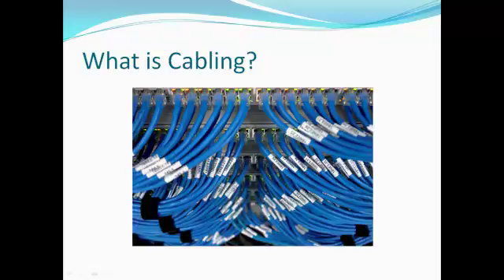Here's another great example — if you look at the actual cables themselves, the cables have been labeled for where they're going. That's going to be another big aspect of cabling. It's not just the physical bundling of all of our cables and putting the physical cable in the correct tray, but also doing labeling of the cable and labeling of the interface. So that when we go to reference our documentation, we don't actually have to go to the wire or go to the device. Our documentation should be so thorough that we should be able to reference it and not ever have to walk into the data center — as long as something doesn't need to be physically moved.